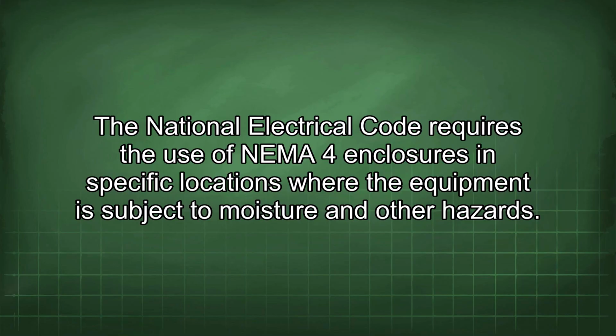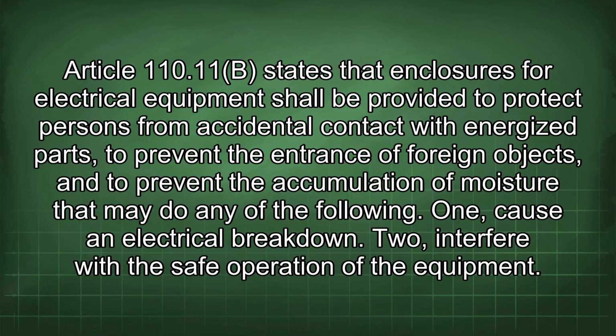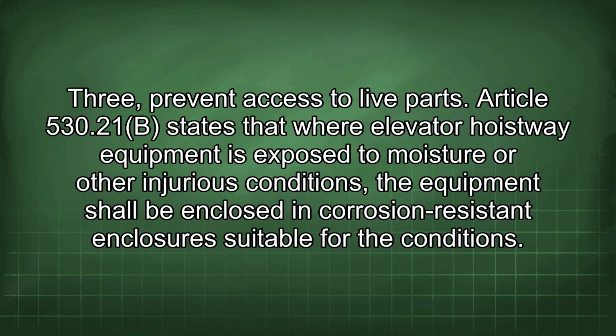The National Electrical Code requires the use of NEMA 4 enclosures in specific locations where the equipment is subject to moisture and other hazards. Article 110.11b states that enclosures for electrical equipment shall be provided to protect persons from accidental contact with energized parts, to prevent the entrance of foreign objects, and to prevent the accumulation of moisture that may do any of the following. 1. Cause an electrical breakdown. 2. Interfere with the safe operation of the equipment. 3. Prevent access to live parts.